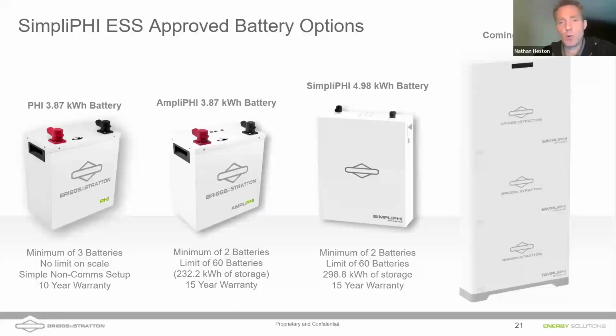We additionally have the 4.98 kilowatt hour battery that's on the screen there. You can parallel up to 60 of the SimpliPhi or the 5 kilowatt hour SimpliPhi batteries. The limitation there is really the closed loop communications, right? If we get too many of them, we'll have too much loss of voltage in those communicating wires. So we can do about 60 of those batteries. That's our limitation. 300 kilowatt hours of storage, that's huge, right? A single Powerwall is 13. We're looking at 300 kilowatt hours of storage here.